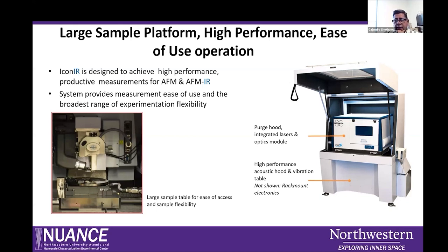It has a closed enclosure, and then we are purging this enclosure with air. So that means basically you have to keep the humidity level pretty low so you can minimize your background noise. At the same time, there are certain interlocks or protections here. That means when the door is open, the laser will turn off. It's an IR laser, so we cannot directly expose our eye to the IR laser. That's why this protection is there. When the hood is open, the IR laser is shut down. When the hood is closed, the IR laser is on.